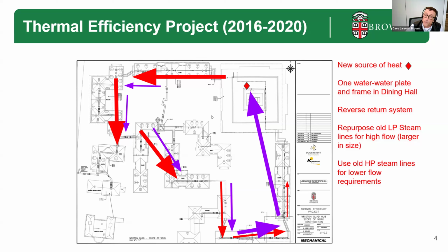We had not only low pressure steam lines here, but also high pressure steam lines, which were smaller. They devised a reverse return system where we used the larger lines in the first part of the loop for the supply, then switched over and used them for the return because we had more flow on the return. We used the high pressure steam lines, which are smaller, on the other side.